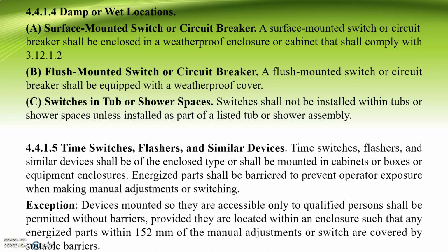Chapter 4.4.1.5. Time switches, flashers, and similar devices shall be of the enclosed type or shall be mounted in cabinets or boxes or equipment enclosures. Energized parts shall be barriered to prevent operator exposure when making manual adjustments or switchings.